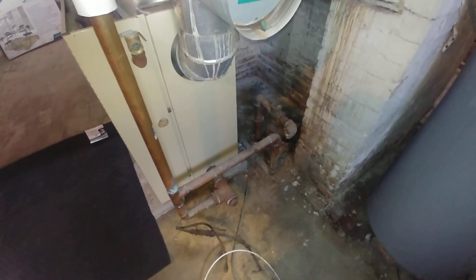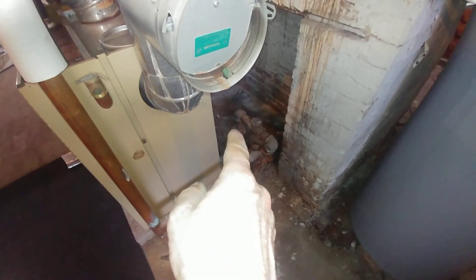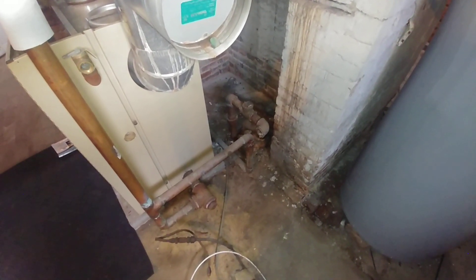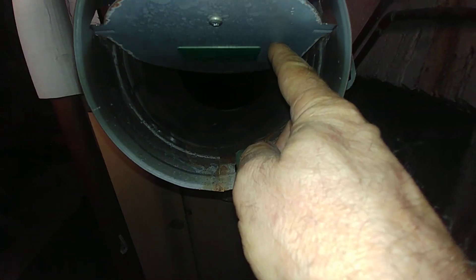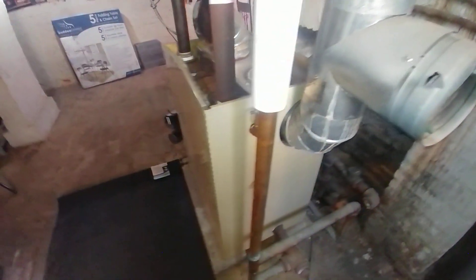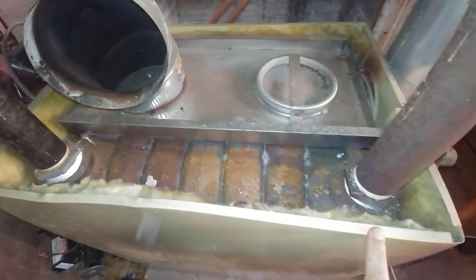There's the return — not quite a Hartford loop, but there it is. There's the leaking return which was replaced way too late in the boiler's life. The oil lines are there; I think it sooted up a couple of times before its final demise. Seven sections total.